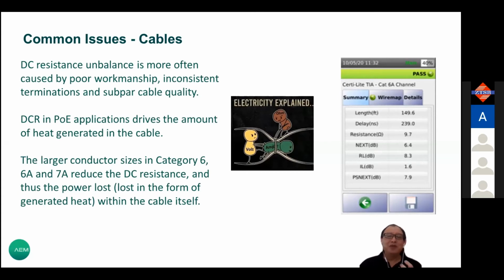If you look at your power cable compared to the twisted pair cable, the significant difference is the copper size. Power cable is usually very thick, can be 16 gauge or 18 gauge, or even as thick as 10 or 12 gauge. But a twisted pair cable is usually 24 gauge or smaller. Now Cat 6 or Cat 6A, we're going higher up to 23 gauge.